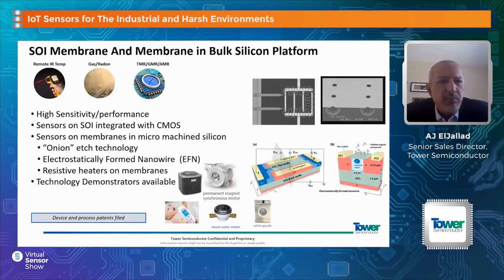The third platform is SOI, silicon on insulator. These sensors typically operate in the subthreshold region, resulting in very high accuracy and sensitivity. You can create remote IR temperature sensing or thermometers with these sensors, as well as gas and radon sensors and magnetic sensors with this platform.